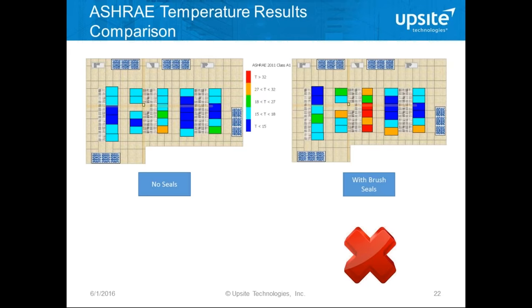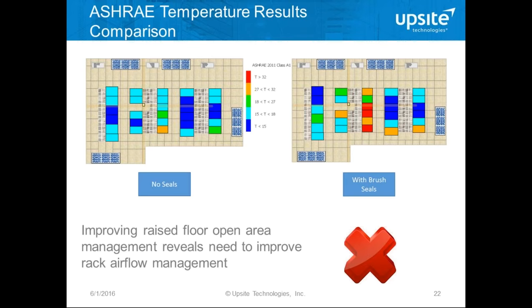When we add the brush seals, things haven't got better — this is a disappointment because it's definitely the right thing to do to manage that lost airflow. But something else is going wrong. Now several of the cabinets are actually above the recommended range. We need to improve the rack airflow management.